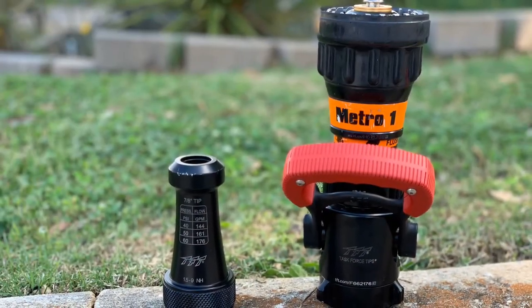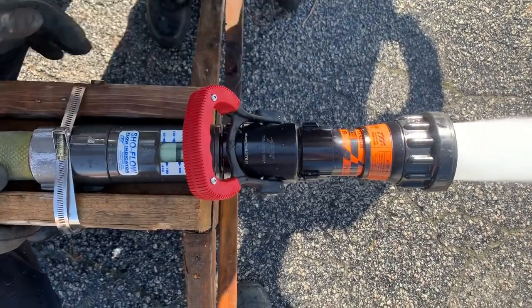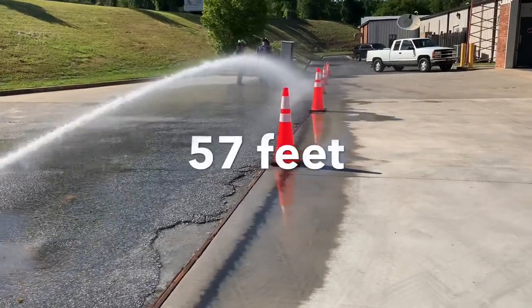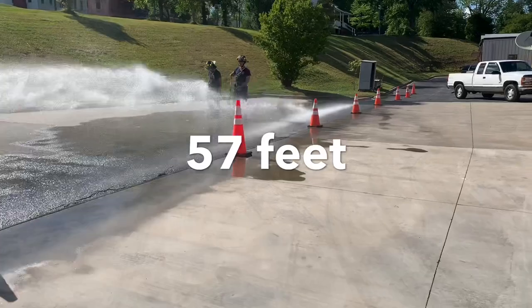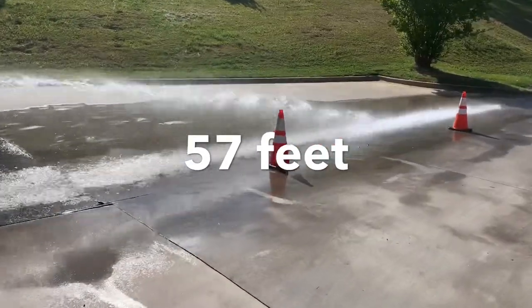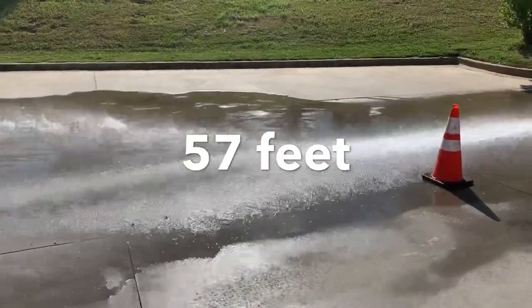Next up is the TFT Metro 1. The bale is a ball shutoff — this is a solid stainless steel ball — and we're starting with the fog nozzle. You can see right away we're flowing 160 GPM at 50 PSI, and we are getting better reach out of the ball valve. We actually achieved about 10 feet more reach. We're at 57 feet before the stream falls. The only difference is the ball valve.